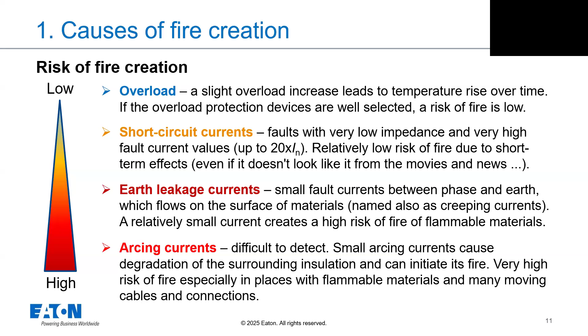In the end, something really dangerous is created when an arc between phase and neutral, or between phase and ground, or also in serial connection occurs. The problem with this kind of fault is that it is really difficult to detect. If such an arc, similar to a leakage current, is present for a long time, relatively small arcing current can initiate fire. This is very risky, especially in places with flammable materials and many cables. Please keep this scale of importance in your head.